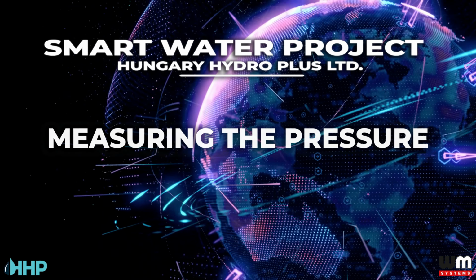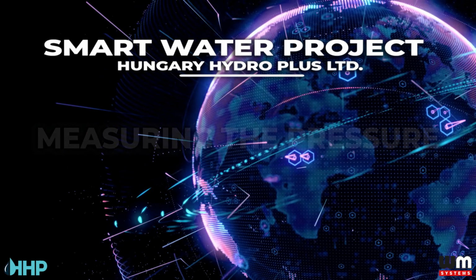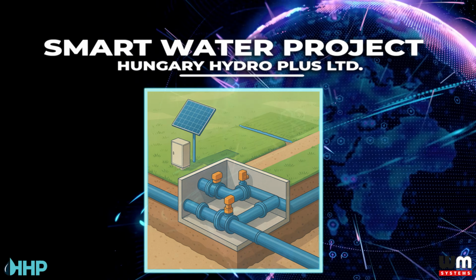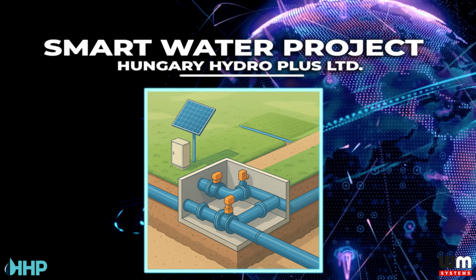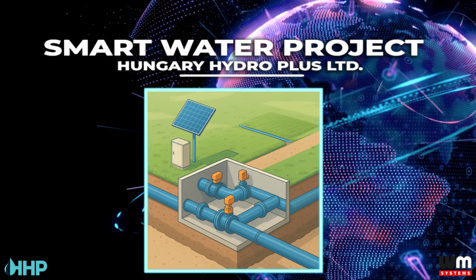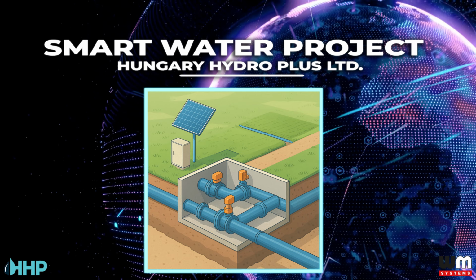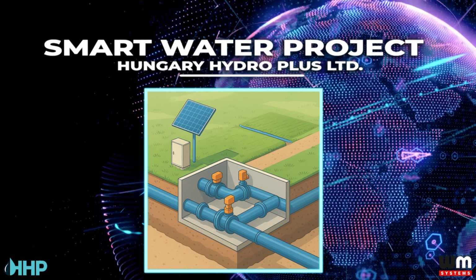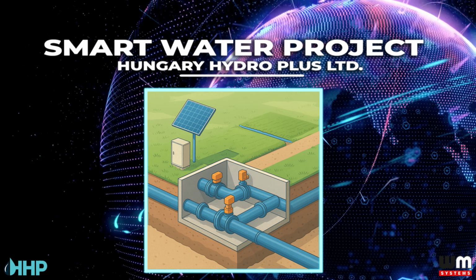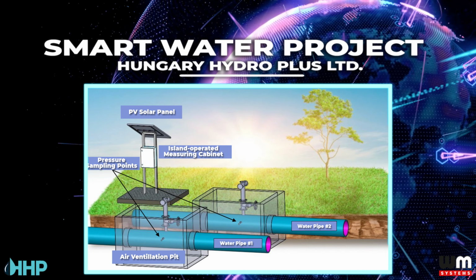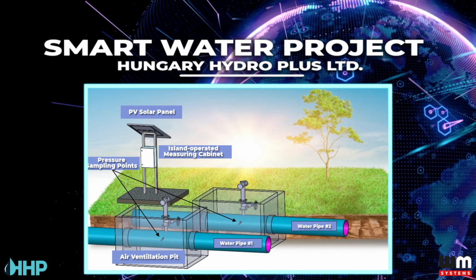Measuring the pressure. A primary objective was to measure pressure loss in real time following the booster pump stations. In a closed system, pressure levels should remain constant. Therefore, any drop in pressure could indicate water loss or equipment malfunction. The system was designed to instantly detect these anomalies and report them to the central monitoring center.